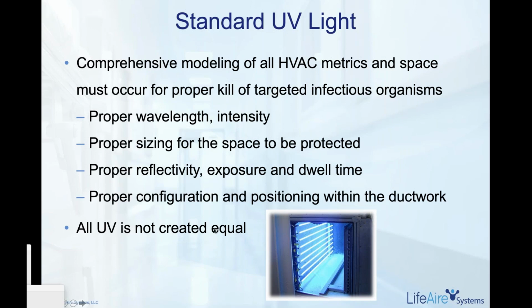What I mean by that is for UV to be completely effective, you need to consider and model all of the HVAC metrics. So the ductwork, the size of the ductwork, the course of the ductwork, the air handler, the space you're trying to protect, the air velocity.